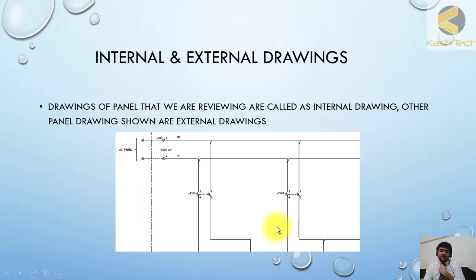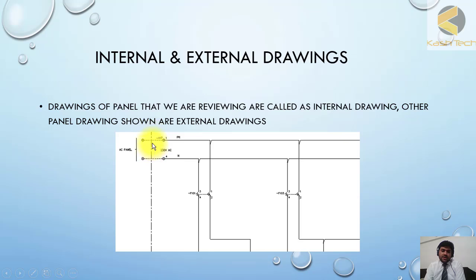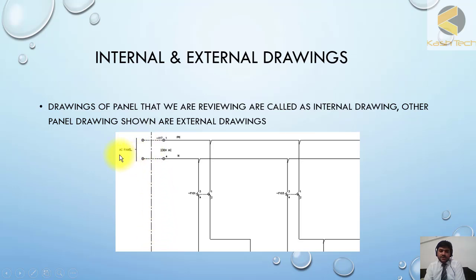This is the drawing of a protection panel in which AC supply is coming from outside. Here you can see it's coming from AC panel. This area, you can see the dash and dot lines are showing that this is external wiring. This is called external drawing, and this is called internal drawing.